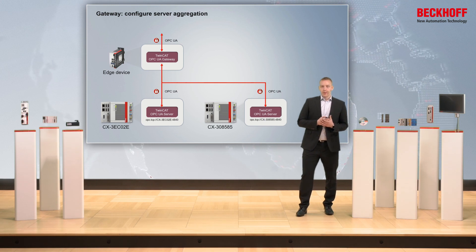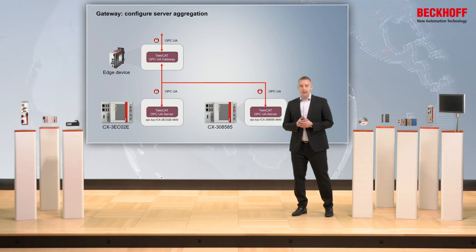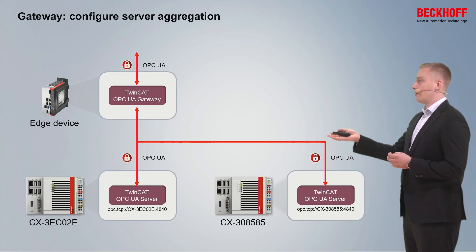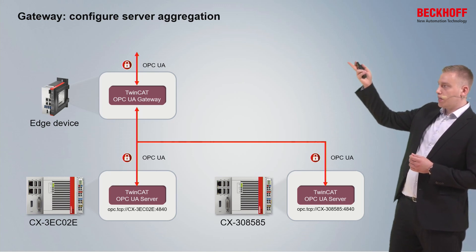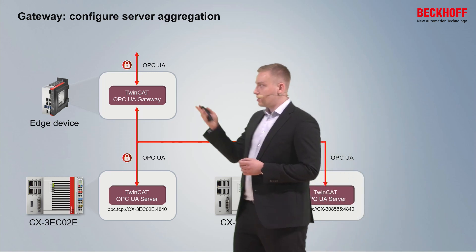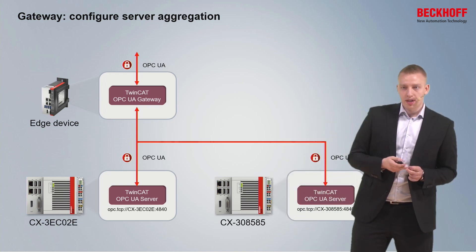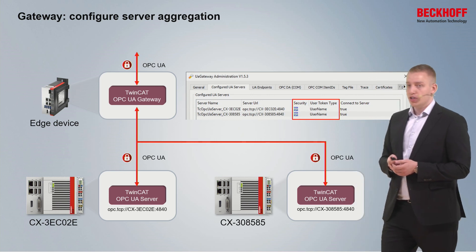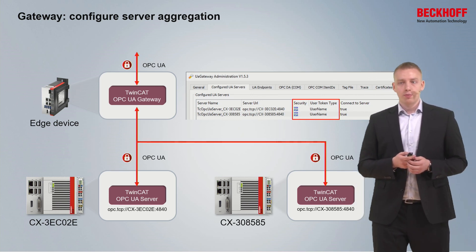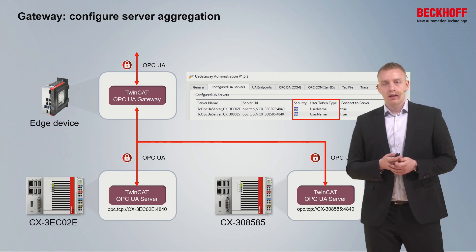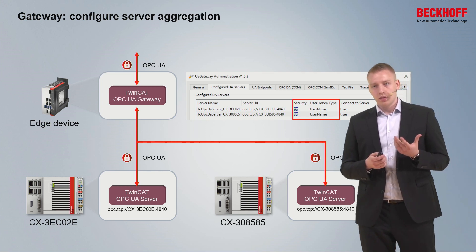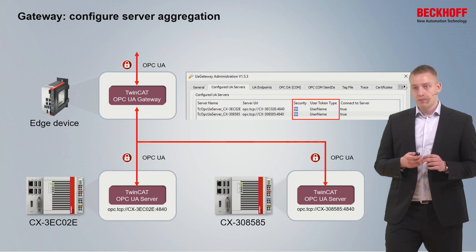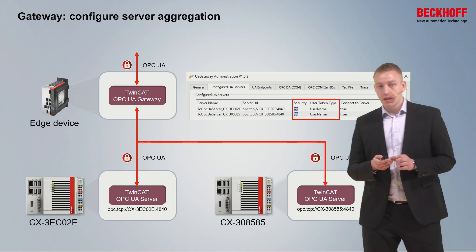Now let's look at the TwinCAT OPC UA gateway. One key use case is server aggregation: two controllers with integrated OPC UA servers are aggregated by the TwinCAT OPC UA gateway. A client connecting to the gateway can access both underlying servers with a single connection. The connection to the underlying OPC UA servers is only configured on the gateway side, so the client only needs to manage its connection to the gateway — the gateway completely handles the underlying connections to both OPC UA servers.